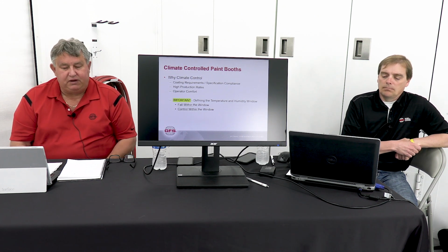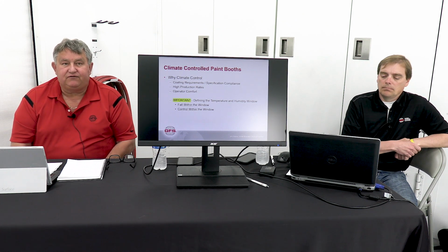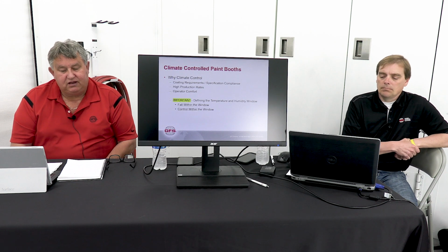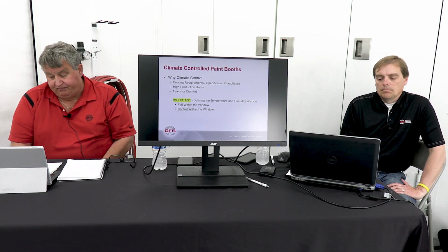20,000 CFM of airflow could be a $250,000 air handling unit alone if it's 100% in, 100% out. If we can reduce that and only do 5,000 CFM of fresh air, recirculating the rest, it may cut that down to a $75,000 air handling unit, with the requirements changed to the booth for LEL monitoring and other things that need to be done to a paint spray booth. There are less expensive options out there too, such as DX cooling or a swamp cooler, if only cooling is required. Those are the things we need to get worked out in answering the RFQ forms properly, so we can turn it over to engineering.